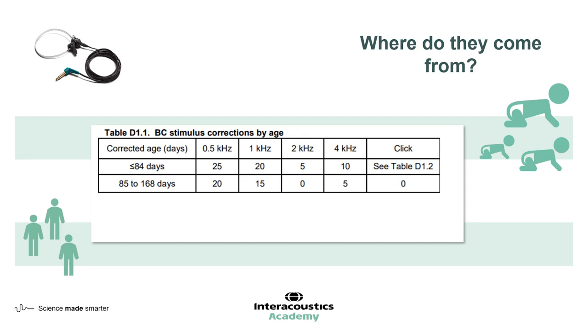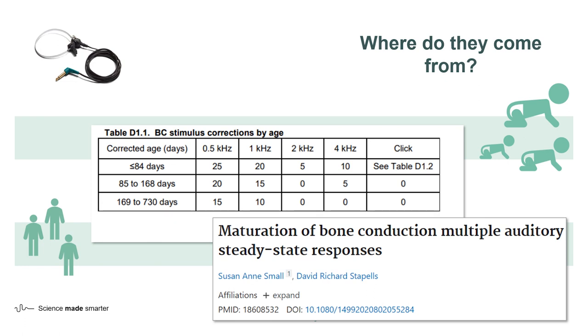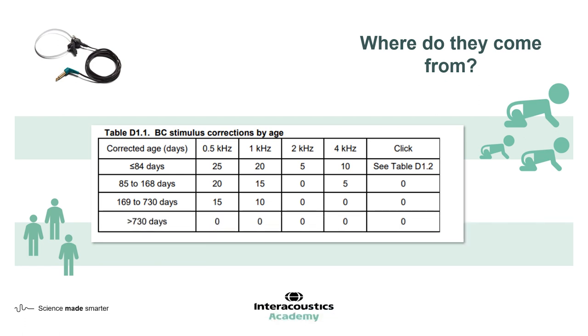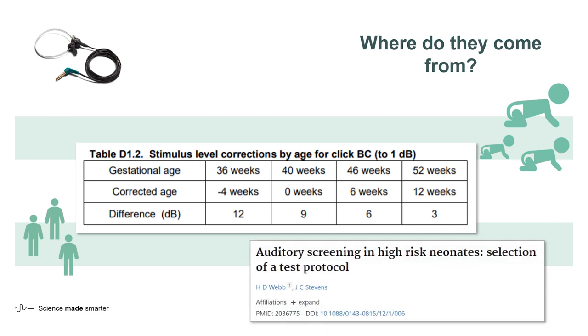Over 12 weeks of age, the bone conduction stimulus correction is retained for all frequencies, but there is a reduction of 5 dB. This is based on evidence from the Small and Stapells paper in 2008 that showed a continued presence of bone conduction stimulus lift above the age of 12 weeks. There is some evidence that a BC stimulus correction value should be applied for babies between the corrected age of 24 weeks and 2 years, with values being adjusted by a further 5 dB, unless the value was already at 0, as in the case of 2 kHz. There is no bone conduction stimulus correction over the age of 2 years. Click bone conduction correction factors are derived from the difference between air conduction and bone conduction click ABR thresholds in babies with normal air conduction click ABR thresholds, as reported by Webb and Stevens in 1993.